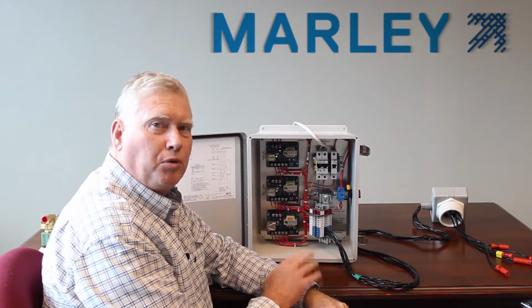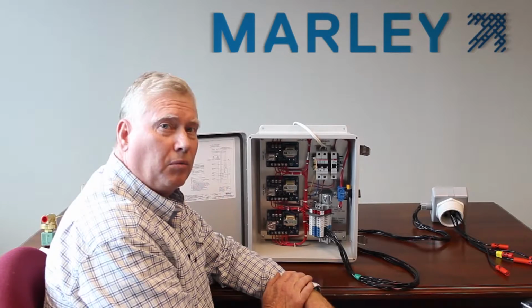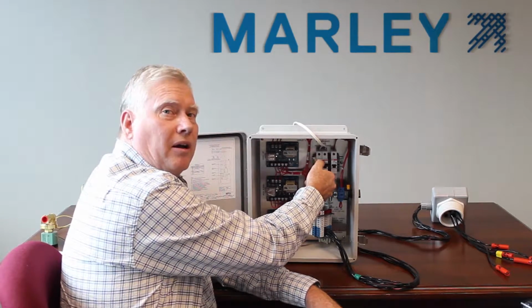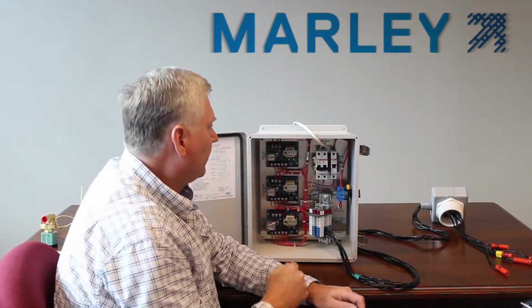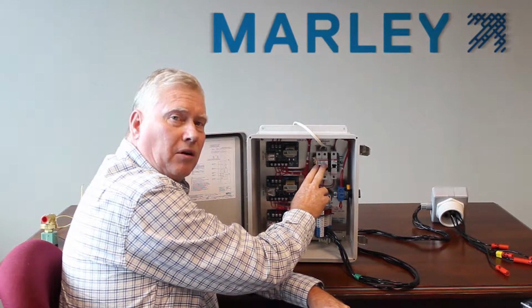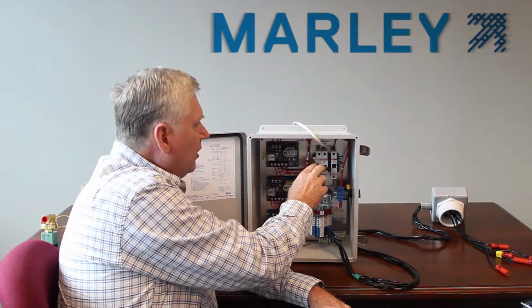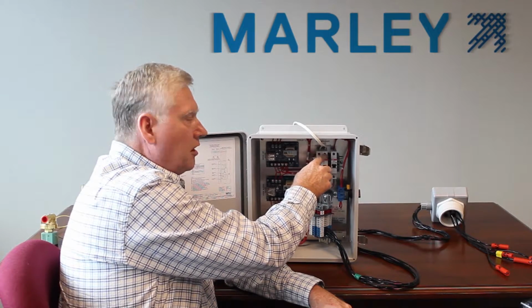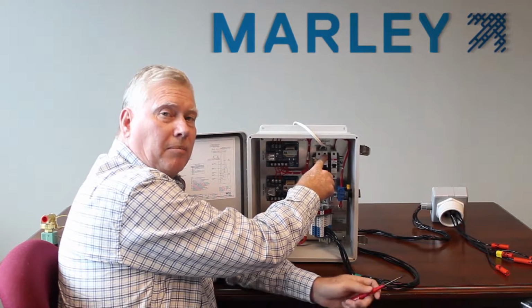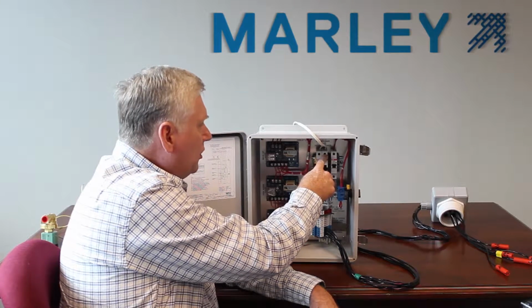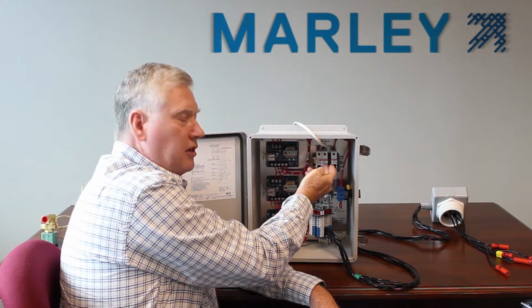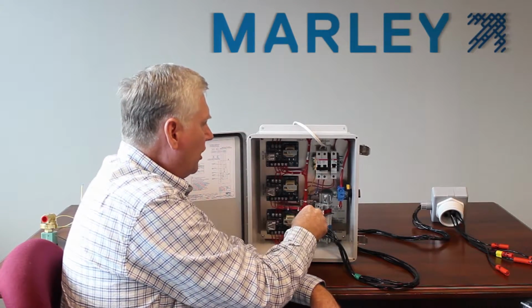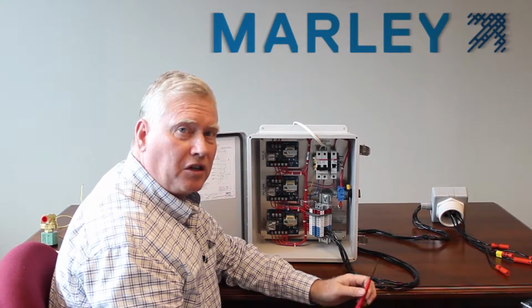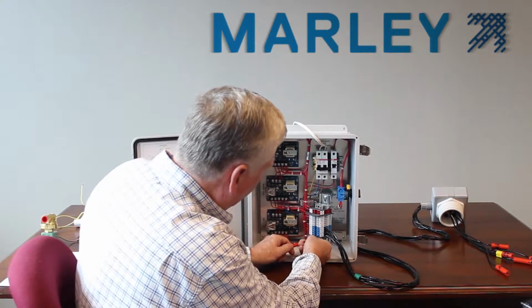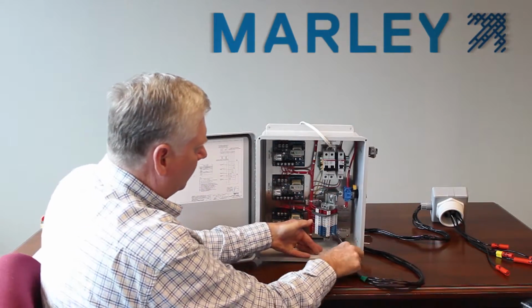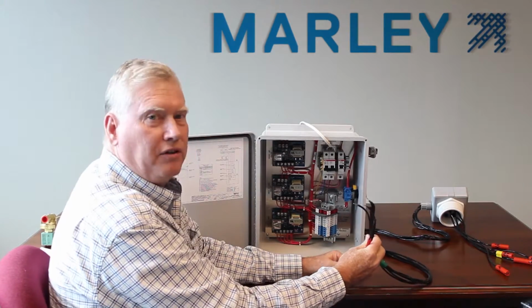So the first thing we're going to do is prove that our panel works. Let's go ahead and disconnect the field wiring. I'm going to turn power off to the panel so I'm safe. Now even though I've turned power off to the panel, everybody must understand that these 2 points up here have 120 volts from the field wiring from the power supply feeding this panel. But I do not have any power after this because there's an air break switch in here, so everything after here is safe. So the first thing I'm going to do is disconnect the field wiring probes. Okay, all the probe wires are out of the system right now.